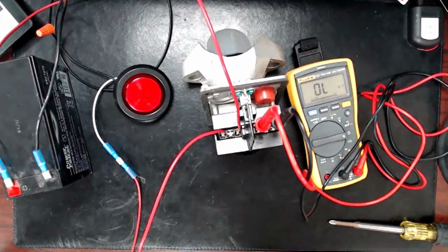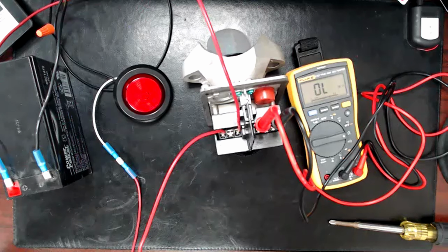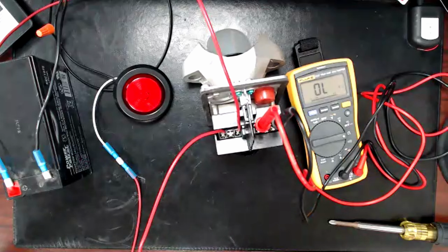The other reason we do it differently with the Silent Night panels is not only is it easier for y'all to install, and anything we can do to make it easier and quicker to install is a good thing, but also those Silent Night panels don't have an auxiliary 24 volts on them. We have to program one of the NAC outputs to be 24 volts. And so if we're already programming one of the NAC outputs so that it can't be a NAC output and it has to be something different that's dedicated, might as well dedicate it to the sprinkler system or to the bell and make it easier for y'all.